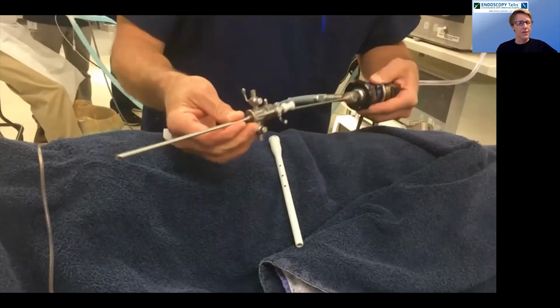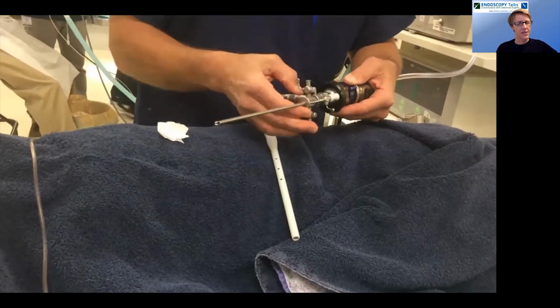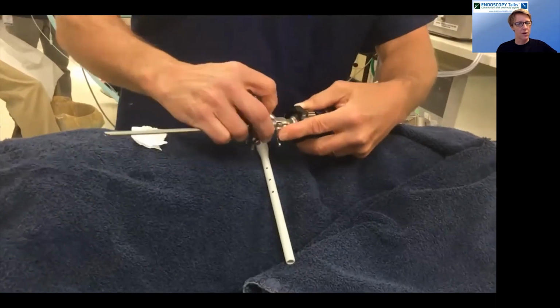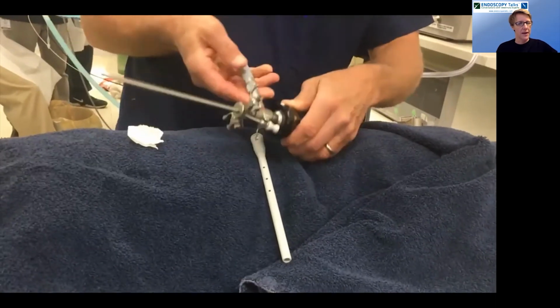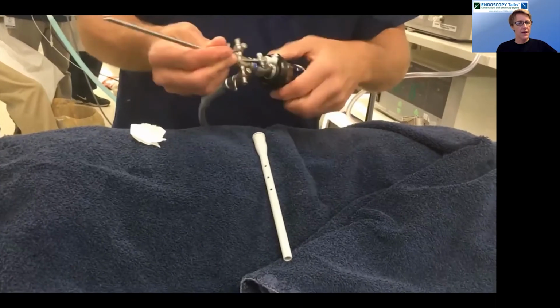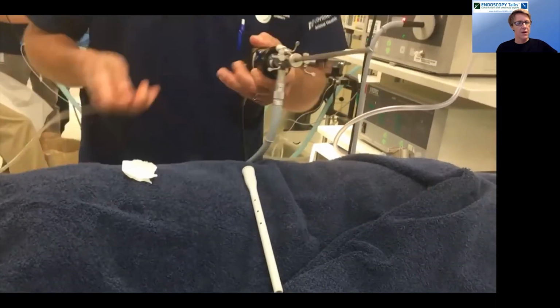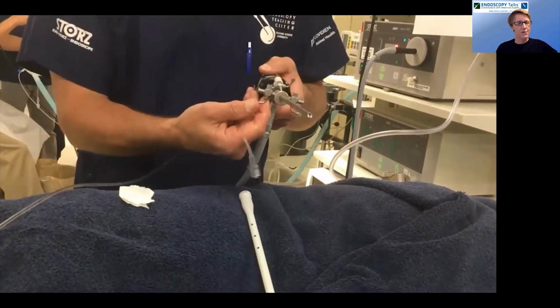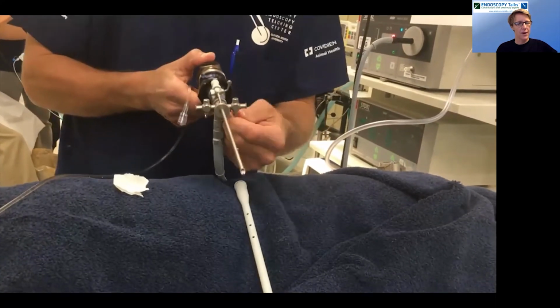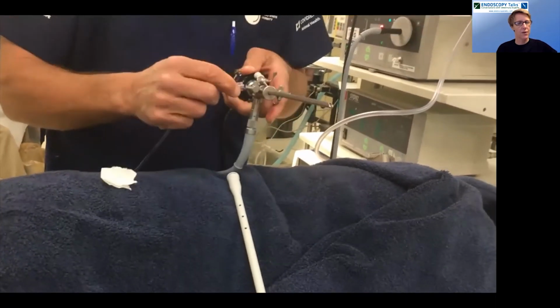Then whichever sheath you decide to use, depending on the procedure, you just slide that over the top of the endoscope and lock it into place. And then what you want to do is take the valves, make sure you turn them off. So you've got an ingress and an egress port, and also on your biopsy channel.